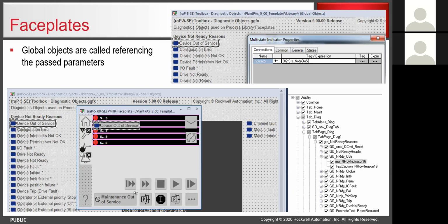I think one of the last things is pretty much all of the Rockwell faceplates have that ISA standard. I think it's 101, which covers basically everything's in shades of gray, so that when things are a nice pretty blue or red or green or something like that, they're of high importance. So you're not seeing a bunch of pretty colors, so the alarm, which is flashing red, is kind of drowned out by all the other pretty colors. Everything's in shades of gray typically, and then you can go in and see exactly, like, well, this is red, that must mean it's important, I'm going to go look at it. So it's easier to find those little things to follow.